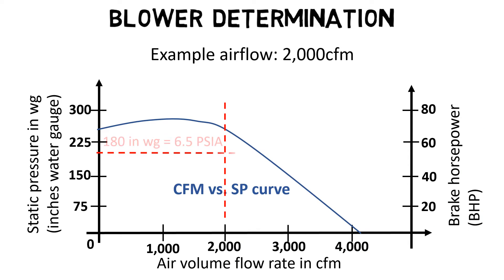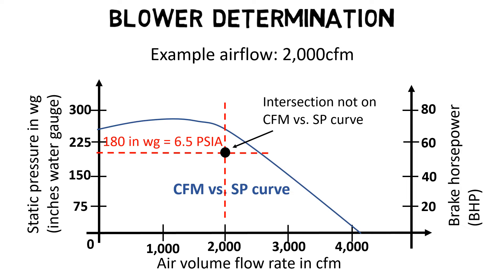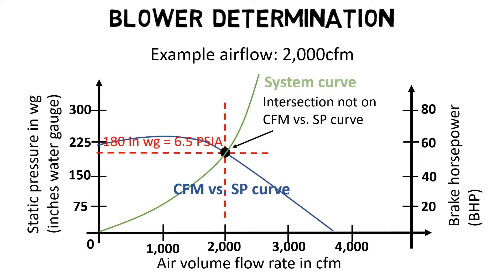Then draw a horizontal line from the left axis until it intersects with the first line. When the intersection of these two lines is not right on the fan curve, you will need to calculate or approximate a system curve and redraw the fan curve at a different RPM level. In our case, we will approximate the system curve. The system curve always has a parabola shape, starting at zero and going through the determined intersection of SP and CFM.